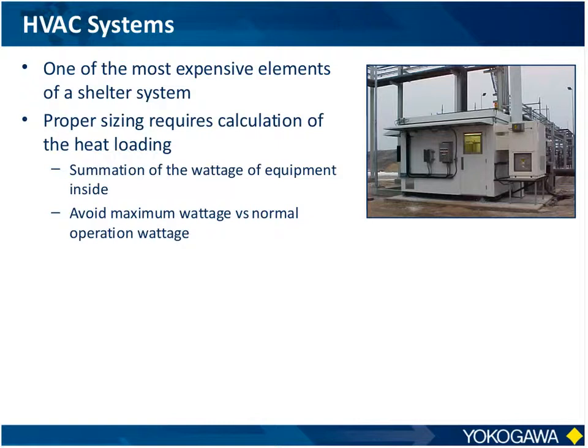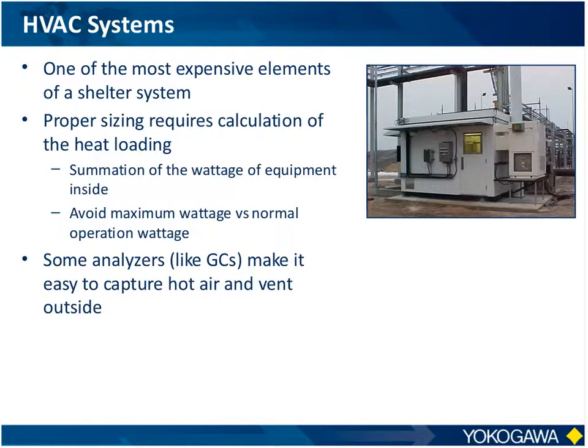Well, when you add up all the wattage inside that shelter, you want to use the 400, not the 1,400, because that's what would normally be seen by the air conditioner, and you would be able to save a lot of cost on the air conditioner by having it sized properly. And many analyzers, like gas chromatographs, make it easy to capture their excess air used in their oven that is very hot and vent it to the outside, so you're just not adding to the load of the air conditioner.